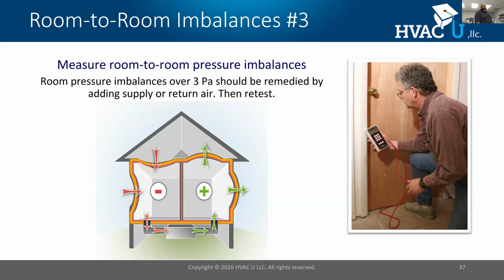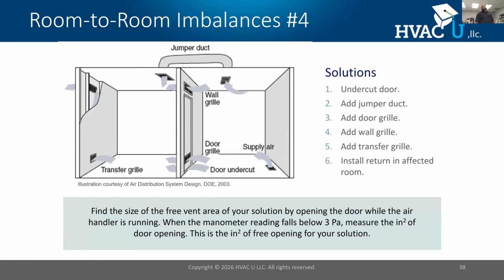Take, for example, a too-much-supply situation, as you see on the right part of the screen here. If I have a supply that is positively pressurizing the building space and I can't get the air out, eventually that room will pressurize to the point where air will stop coming out of the register. But if you need the conditioned air to come out to keep you comfortable, it won't happen. Also, when I positively pressurize that room so much, I now start to get building shell leakage out of that room. So one CFM in, one CFM out. I'm going to pull unconditioned air from another location, and now my air handler has to heat up that air just because I had an imbalance. So these are room to room pressures. The magic number is 3 pascals.